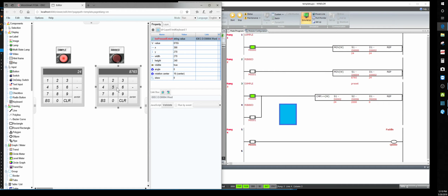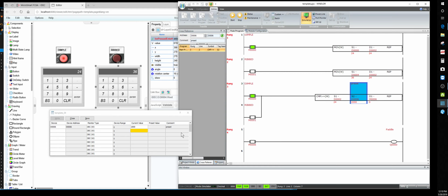Let's go over here. We want to make this one, let's say this one's a 36 box case. Move 36, okay? Now, D6, let's put that at 0. Here's our D6 is 0. So this is greater than that. This is our counter, so this is on. And we go D6, let's say 24. It's equal to that, so it's staying on. We go 25 pulses, that goes off.